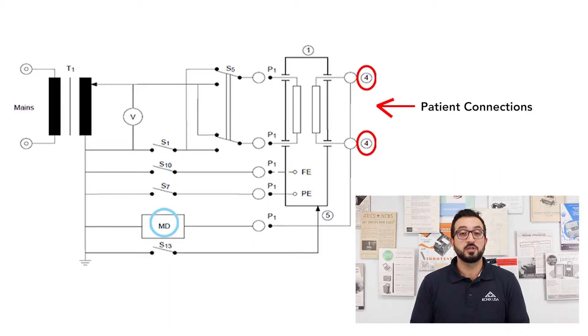As you can see in the image, in this case the measuring device circuit is placed between the patient connection and the low side of the power supply. This would ensure that any current that flows from this patient connection goes through the measuring device circuit back to the reference.